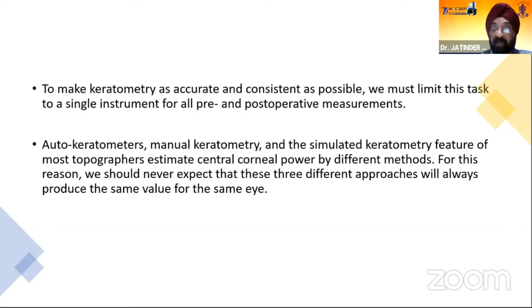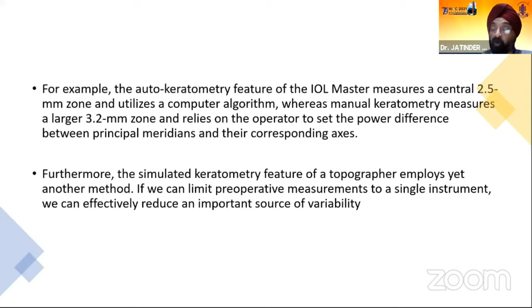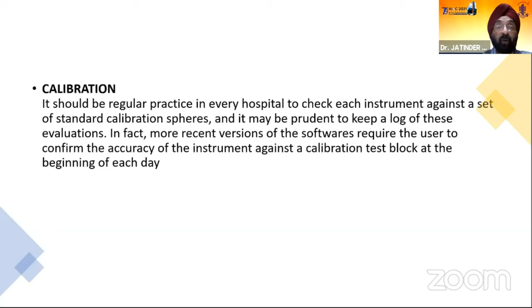For example, auto K measures the central 2.5 millimeter zone, whereas manual keratometry estimates a larger 3.2 millimeter zone, and simulated keratometry employs a different method altogether. It is equally important to calibrate your instruments and keep a log of these evaluations. And recent versions of the softwares require the user to confirm the accuracy of the instrument against a calibration test block at the beginning of each day.